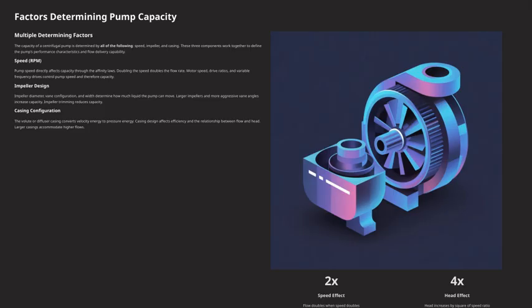Next, the impeller design is crucial. The diameter, vane configuration, and width all influence how much liquid the pump can handle. Larger impellers and more aggressive vane angles tend to increase capacity. Conversely, trimming the impeller reduces capacity, which can be useful for fine-tuning performance. Then there's the casing configuration. The volute or diffuser casing converts velocity energy into pressure energy. Its design impacts efficiency and the relationship between flow and head. Larger casings are better suited for higher flow rates.